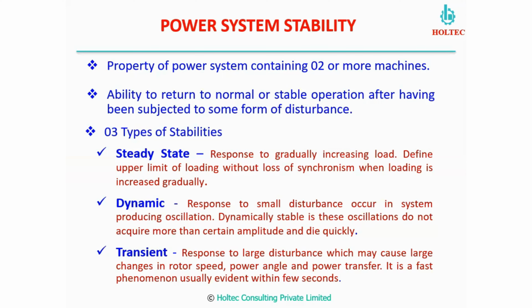Dynamic stability is where small disturbances occur. You can visualize this when you start a motor. There will be a starting kick. This starting kick may be in the range of 6 times, 7 times, or 200% or 300%, depending on the type of starter. So this is a kick load which comes when we start the motor. It gives us a sudden change in the load of considerably higher magnitude, so there will be an oscillation in the operation.